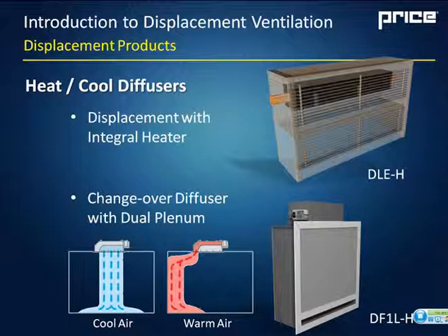Now we also have a variety of heat-cool diffusers, which is a new concept. We have the displacement with integral heater, where along the bottom is the displacement diffuser, so you have your cool, low-velocity air provided through the bottom of this, and there's a plenum on the back. And then on top you have your fin tube heater or your electric heater to provide your conditioning of the skin loads. So these are very popular for office buildings or for schools as well, where you have a lot of perimeter glass, a lot of perimeter wall to condition, and you need to provide the air volume as well for either ventilation in the winter as well as cooling in the summer.